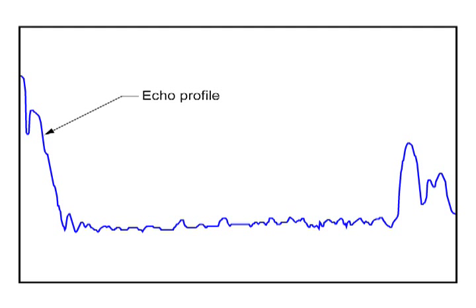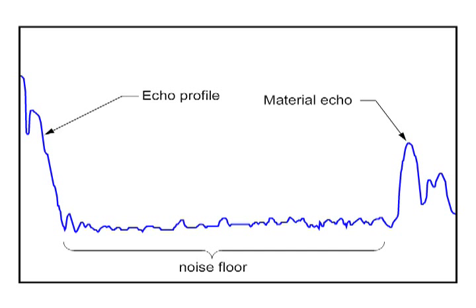At the front end, we have a relatively flat area. We call this the noise floor. This is background noise. The large bump on the echo profile is our true material echo. The smaller bumps following the true echo are indirect or false echoes.